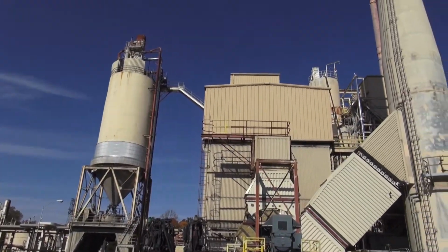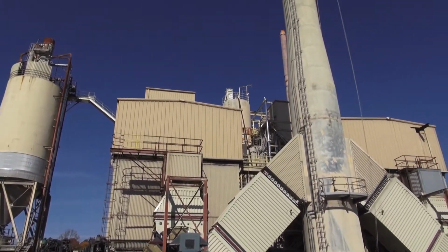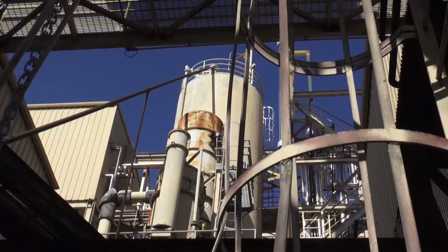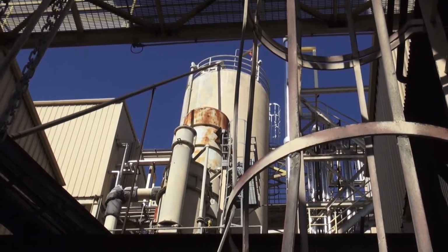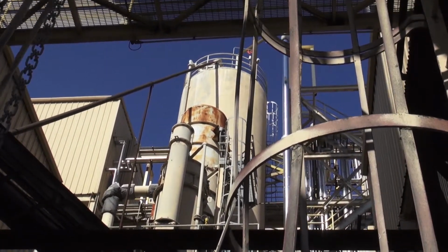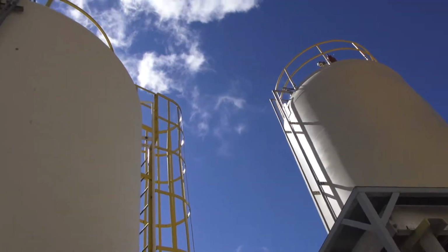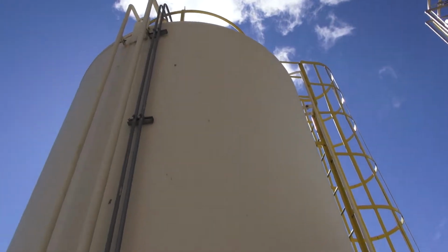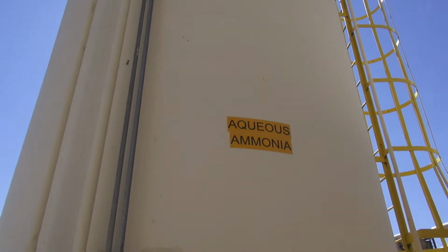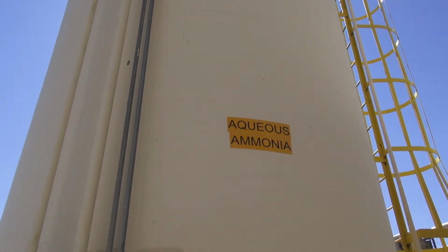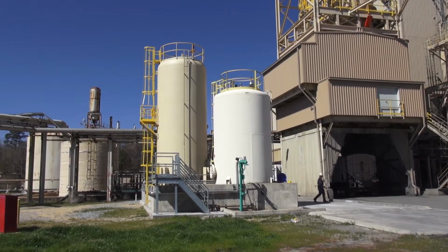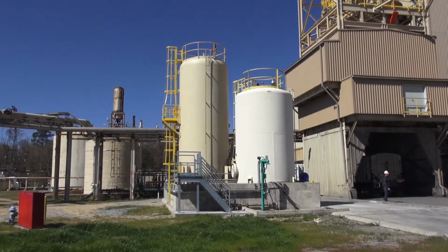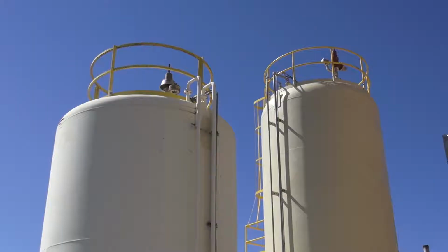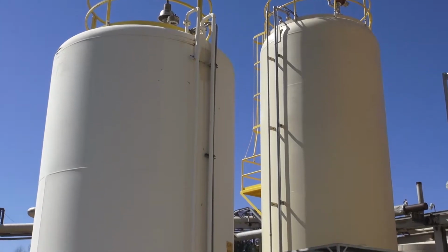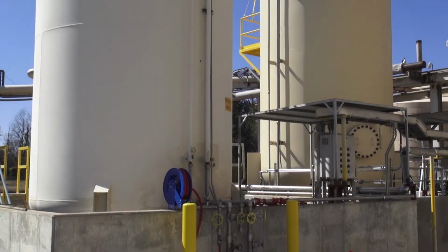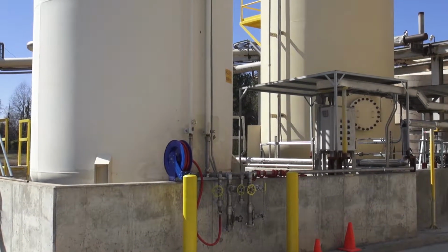At the south end of the plant is a silo filled with lime. When combined with water, this material is extremely caustic and produces a large amount of heat, capable of causing extreme burns. Just southwest of the ash silo, there are 2 aqueous ammonia storage tanks. These tanks contain ammonia at a concentration of 19.5%. Special PPE is required when working with this equipment. The easily recognized odor of aqueous ammonia provides adequate warning of its presence. If encountered, stop all work, exit the area upwind, and notify the control room.